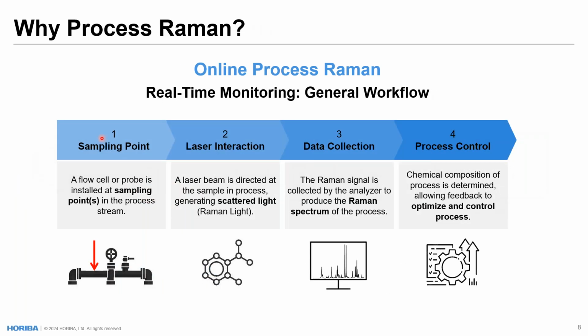So a general workflow for real-time monitoring with online process Raman can be broken down into these 4 steps. The very first thing is we decide on a sampling point with the end user. A flow cell or probe is installed at sampling points in a process stream. What I mean by that is we either take a flow cell enclosure and plumb from the process line into a flow cell enclosure where there's a Raman probe inside that enclosure that reads back into the analyzer. Or another option is using an immersion probe that goes directly into the liquid and constituents of the process stream, as represented by this red arrow here.